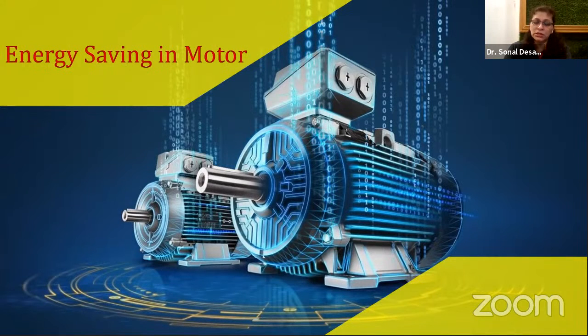So this energy saving in motor is very much important, because there is a huge power consumption in the motor. This is the one which is used universally, the largest used rotational device we can say in the world, that is motor. And it is highly ignored. People don't consider energy efficient motor usage while buying a motor. Manufacturers again, and some more issues with the motor, there are multiple standards. Even in a single country, there exist 3 to 4 standards which a motor has to follow. So a non-technical person will always get confused about which standard one needs to follow.